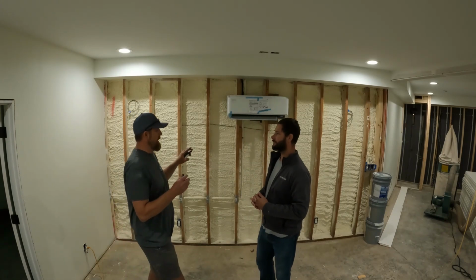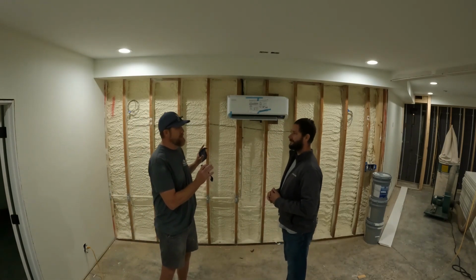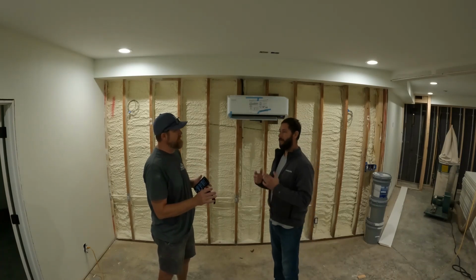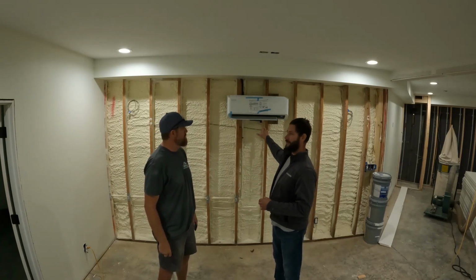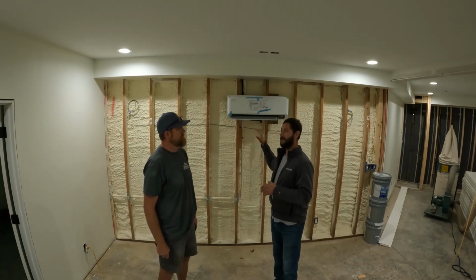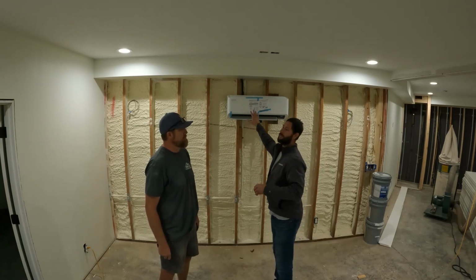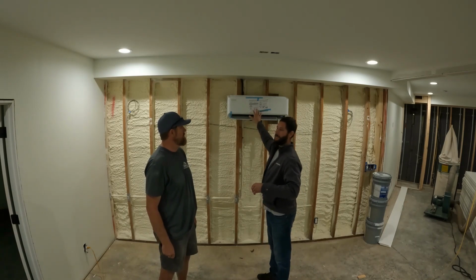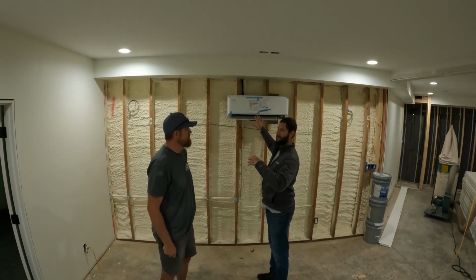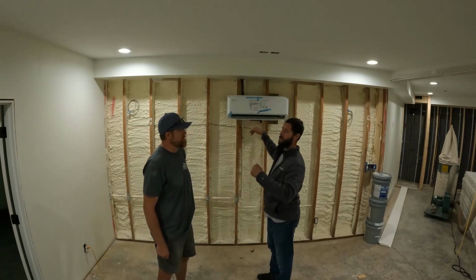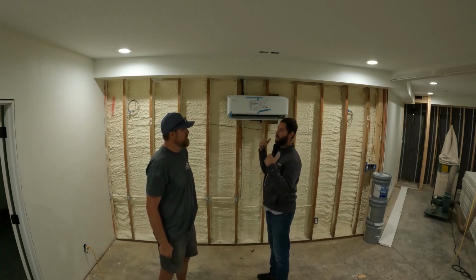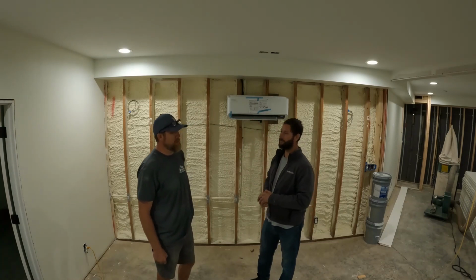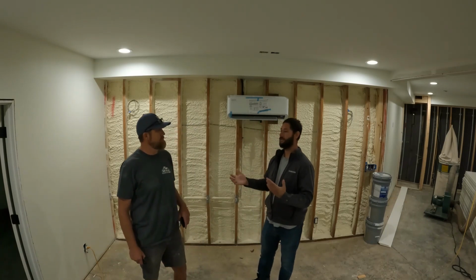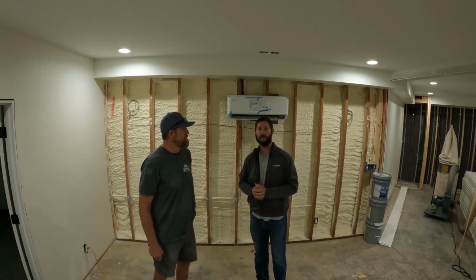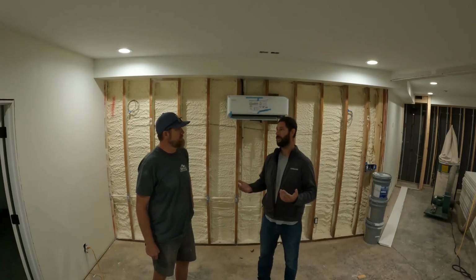Okay, so I noticed that they run pretty constant. That's just a fan basically? Well, in the cooling mode, the indoor fan runs 24/7. It pulls less than an amp. In the heating mode, the indoor fan will not run until the temperature of this coil reaches 99 degrees. Okay. So in heating, they have a temperature actuated fan, and then in the cooling, it's just because of comfort, because you want a consistent amount of airflow in the cooling mode. Okay. All right. So it's great for foam houses where you definitely have to make sure you control humidity. Having airflow is a great way to control humidity.